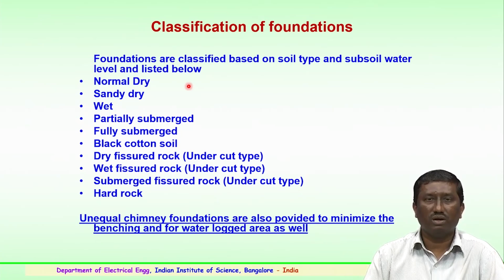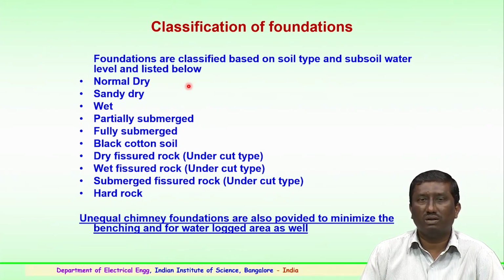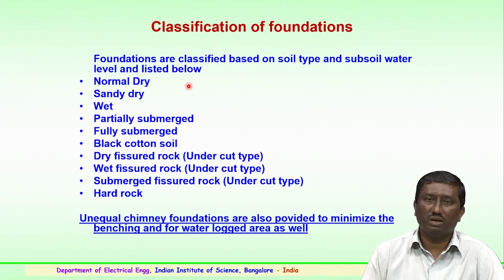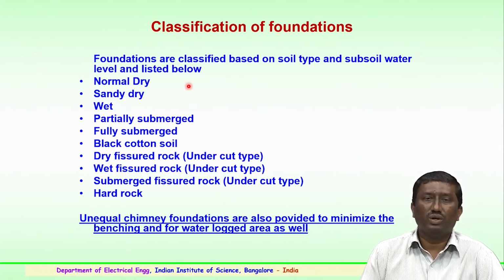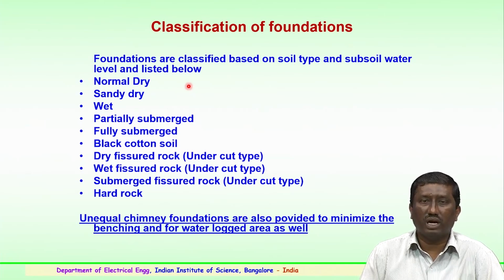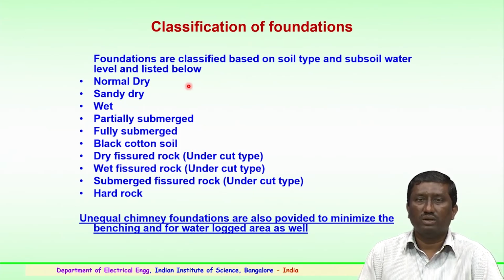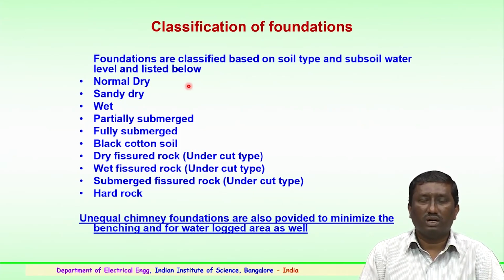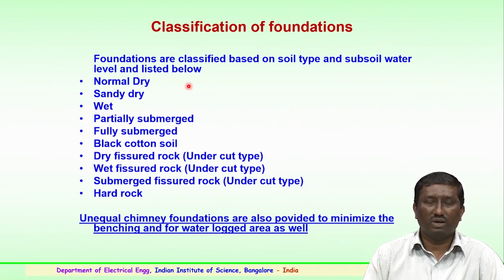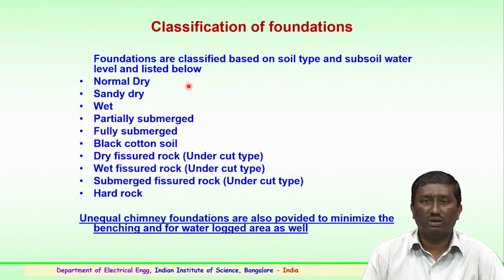So the conditions: whether the soil is dry or wet, partially submerged with water or fully submerged in water, whether it is black cotton soil, or dry fissured rock of the undercut type, or wet fissured rock, or submerged fissured rock. Is the place having hard rock, or is it a mountainous area? Depending upon several of these classifications, the foundations of towers are considered, and for each aspect suitable foundations have to be laid, so that the tower has strength and works for the long period of its life. So this is a very important aspect, and this classification helps in suitably choosing a particular foundation for that area.